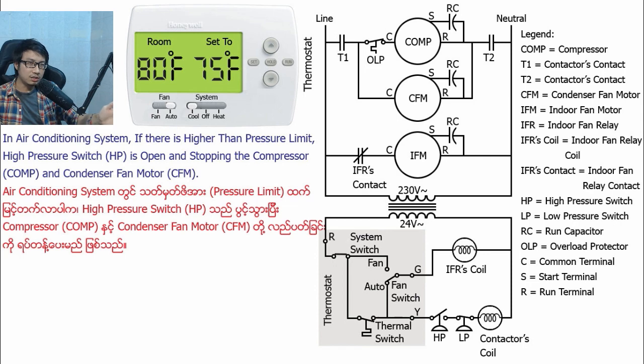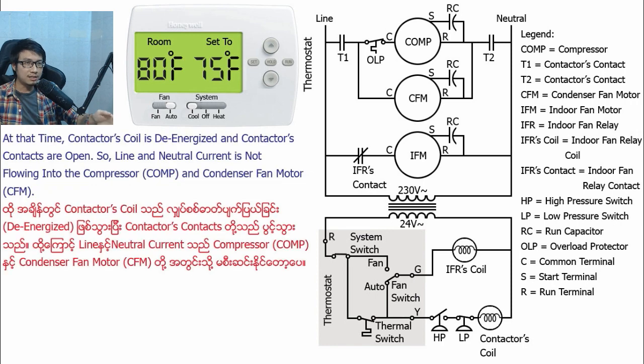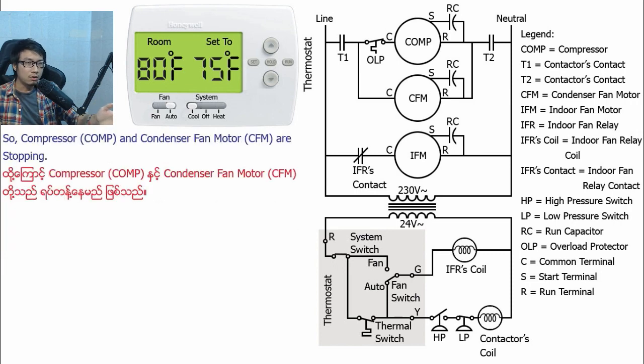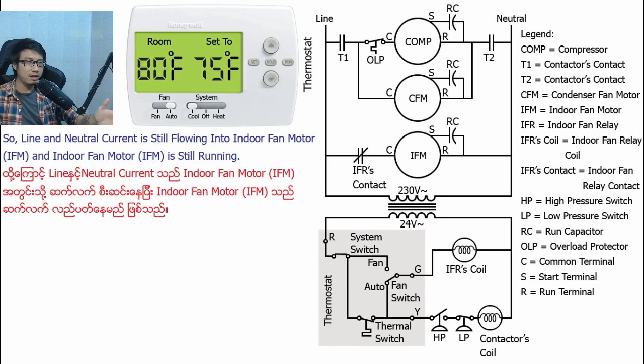In the air conditioning system, if there is a high-temperature or high-pressure limit reached, the high-pressure switch opens and stops the compressor and condenser fan motor, because the high-pressure switch disconnects current flowing into the contactor coil. At that time, the contactor coil is de-energized and contactor contacts are open, so line and neutral current is not flowing into the compressor and condenser fan motor and they stop. In this condition, the indoor fan relay coil is still energized and indoor fan relay contacts are still closed, so the indoor fan motor is still running.